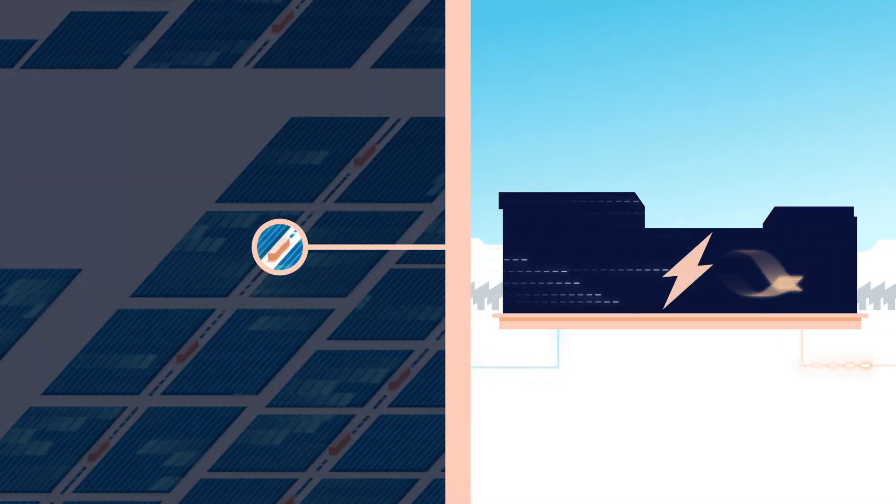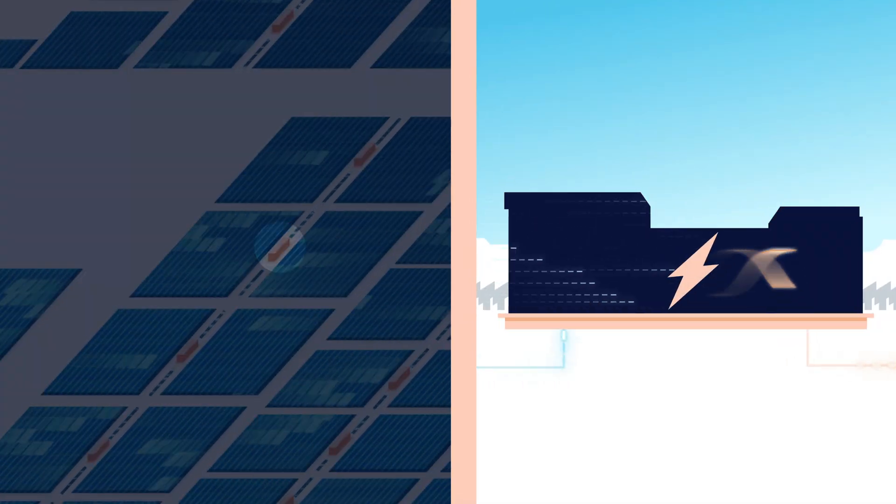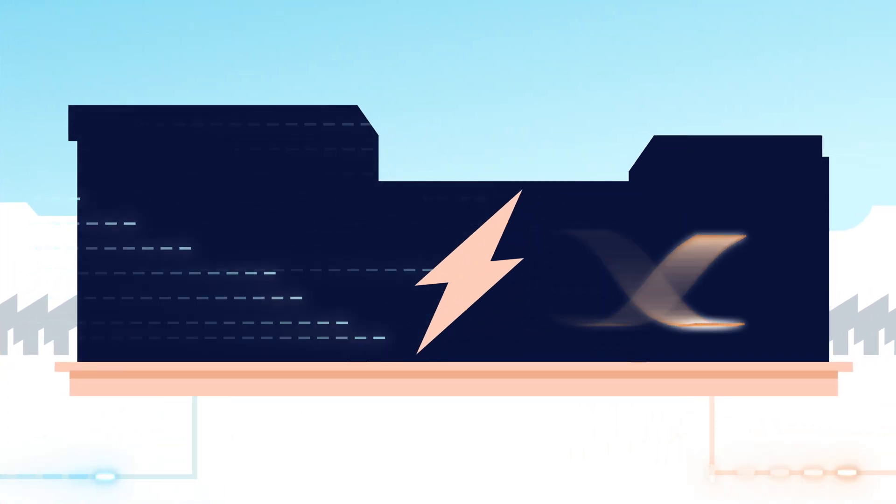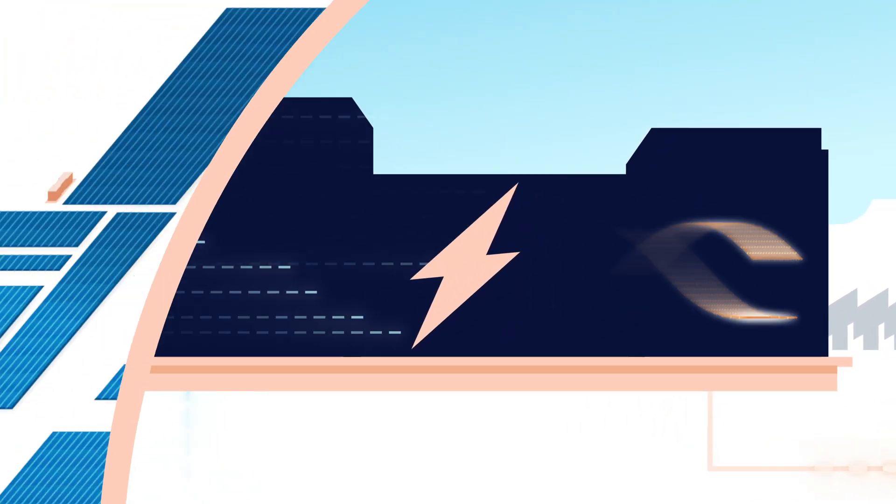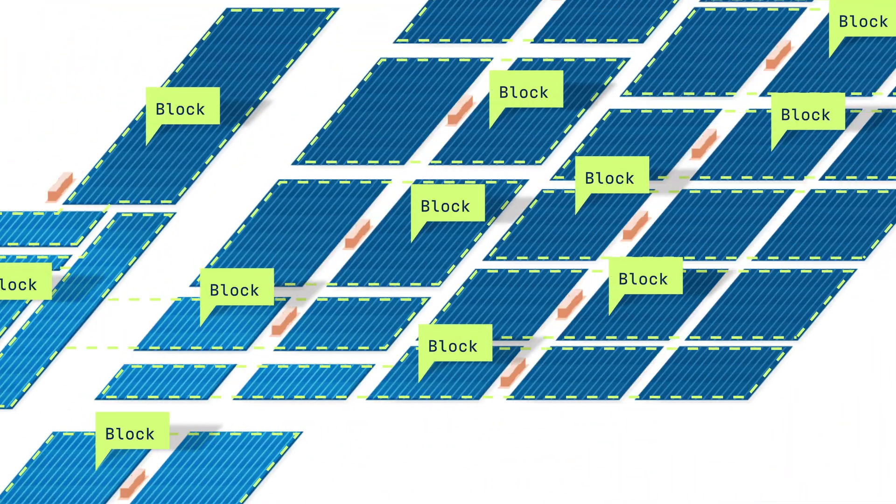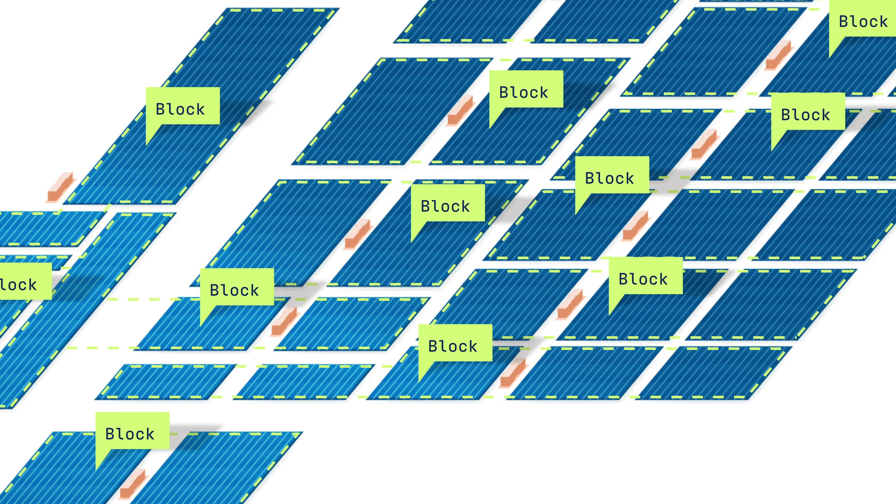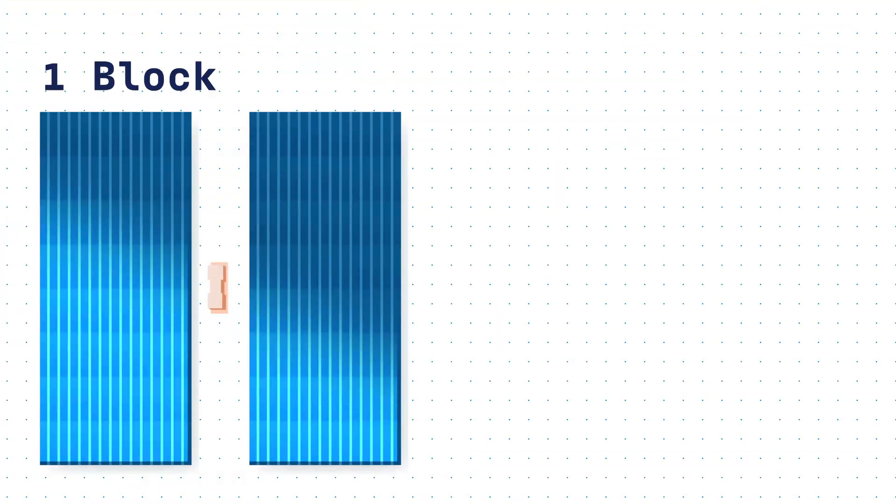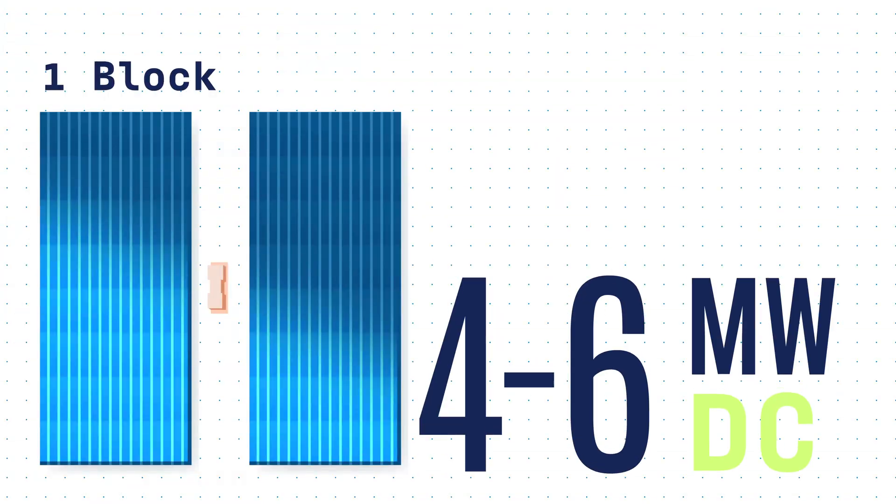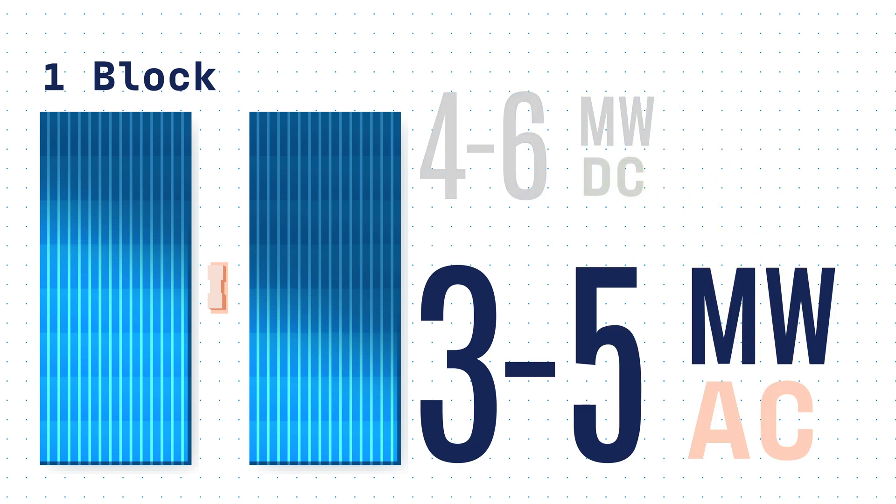At the inverter skid, DC power goes in and AC power comes out. Solar plants are broken into blocks. Each block has one inverter skid. Usually, a block provides 4 to 6 megawatts of DC and 3 to 5 megawatts of AC power.